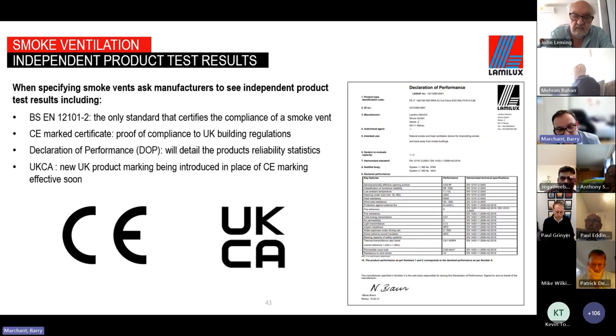The second one is Appendix C, which is the test method for reliability, and I was genuinely gobsmacked when I came across this one. During testing, the unit is put through its paces on an opening and closing function. And there are different levels of smoke ventilation reliability ratings based on the number of opening and closing cycles tested.